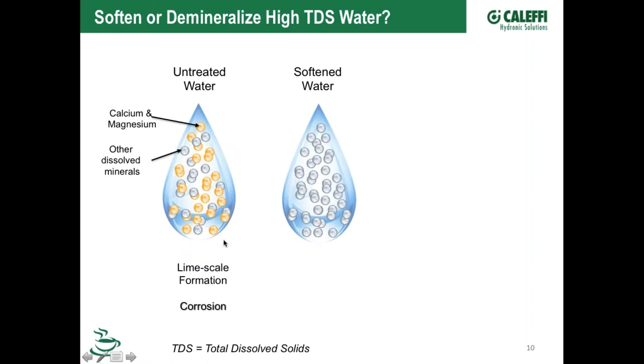So we fixed one kind of bad thing we don't want, which is the scaling minerals. But now by adding all these other sodium ions in there, we've increased the conductivity of the water. And when we have high conductivity water, that still leads to problems with corrosion and aggressive water.